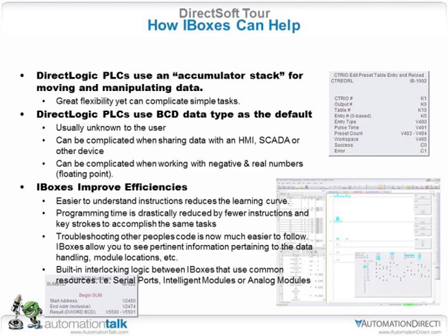With the iBox, everything's in one instruction and everything's labeled. For me, the hardest part with the whole list of load, out, load, out with different constants and variables was trying to make sure I documented that rung, because I might end up with 10, 12, 15 small load and out boxes within that same rung, and to document it meant actually identifying the different V memory addresses and saying exactly what they represented. With iBox, everything's labeled. You're going to put your parameter in there, and you're done.